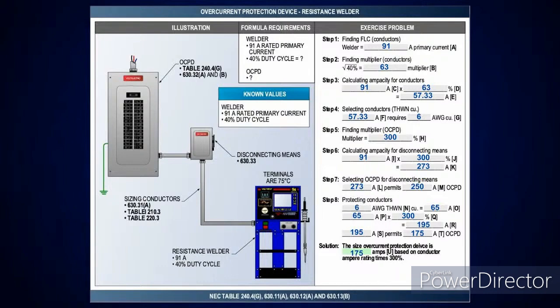Okay. So looking at this, I've got a resistance welder that's 91 amps, and I've got a 40% duty cycle. If I look at table 630.31(A), pick up 40%, it's going to tell me it has a 63% multiplier here. So I'll take the 91 amps times 63%, which gives me 57.33 amps. We've got 75 degree C terminals. I'll look at table 310.16, come down. The next size above that is 65 amps, which is a number 6 conductor. Okay?